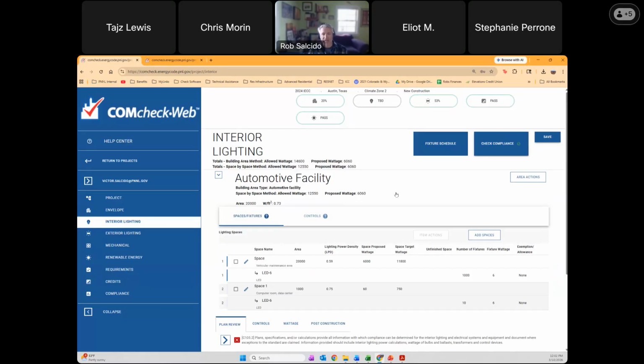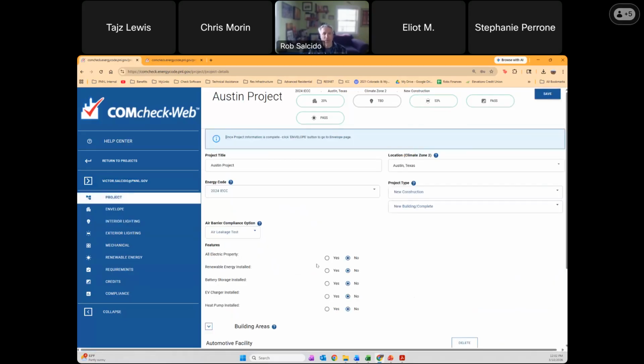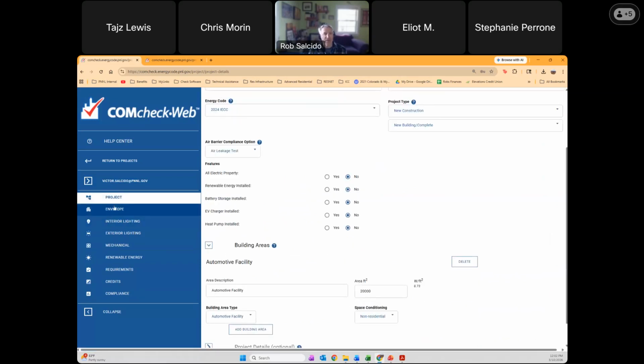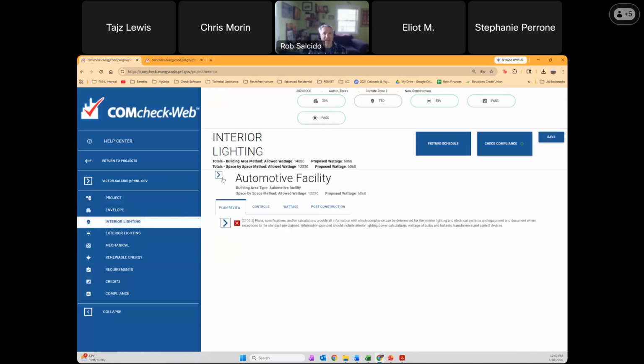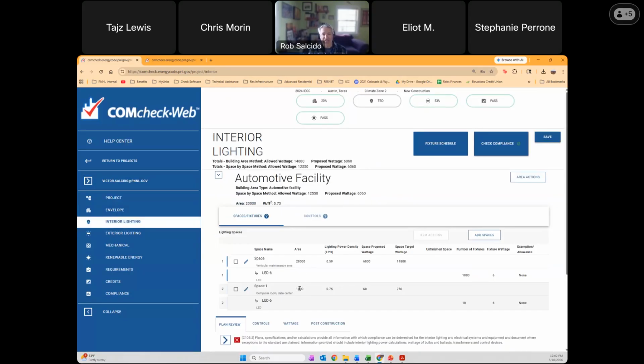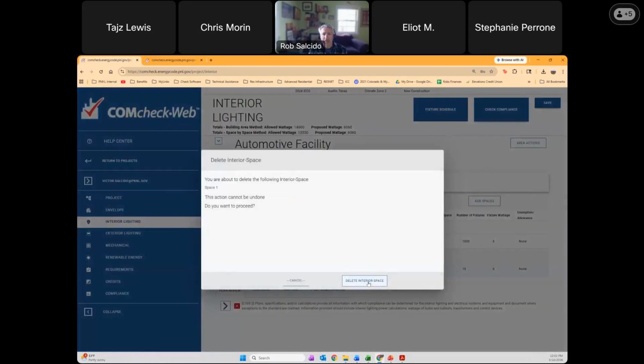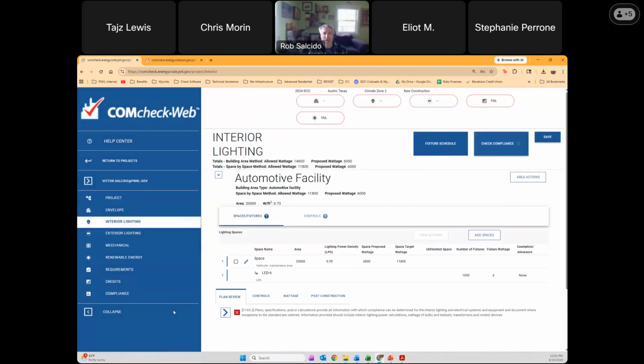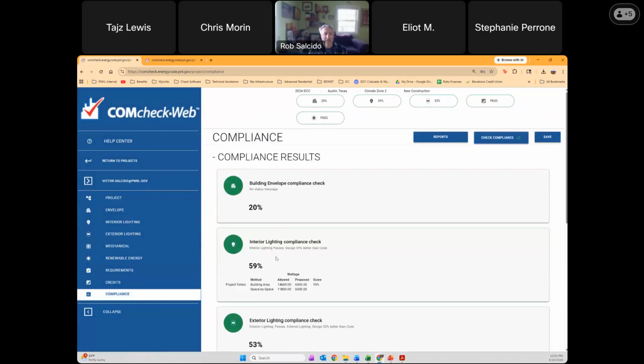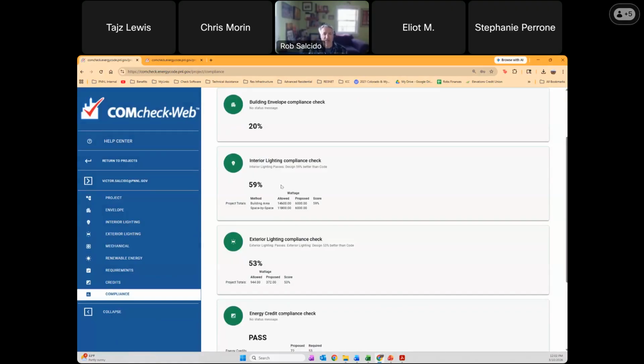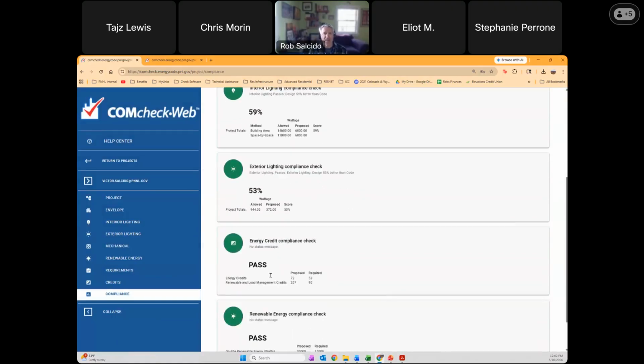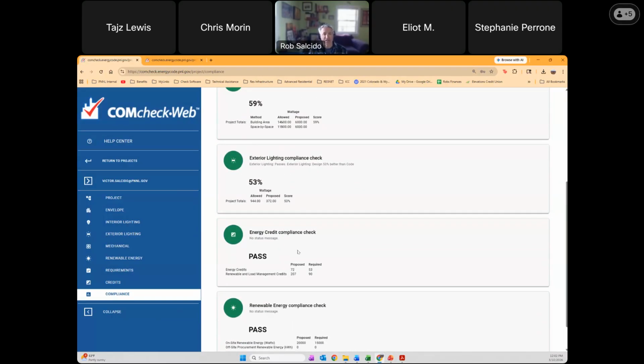COMcheck is going to do a lot of logic checking, and what it's saying is, I've defined my total building at 20,000 square feet, but I've added an extra 1,000. So it's saying you've got too much area of lighting above. So I'm just going to delete this. Now my interior lighting is showing compliant, my exterior lighting is showing compliant. So far so good. We're looking good on our design.